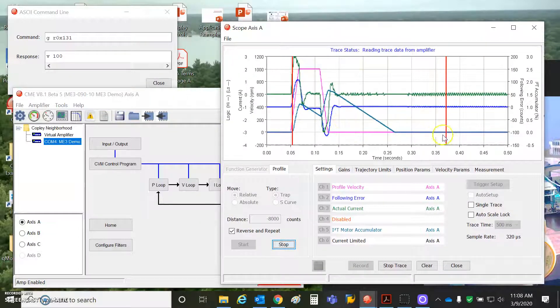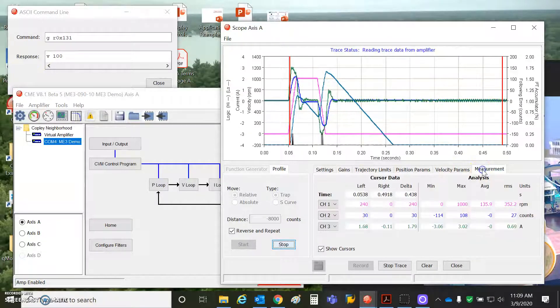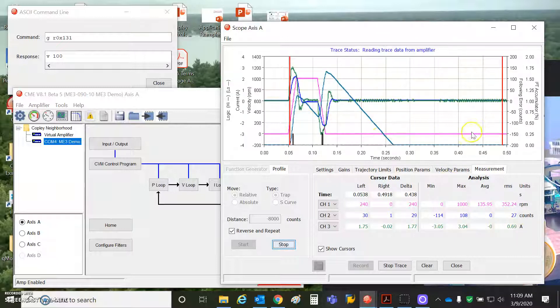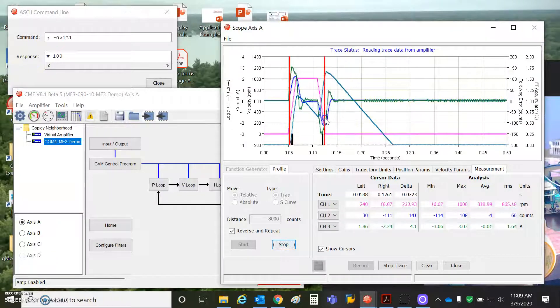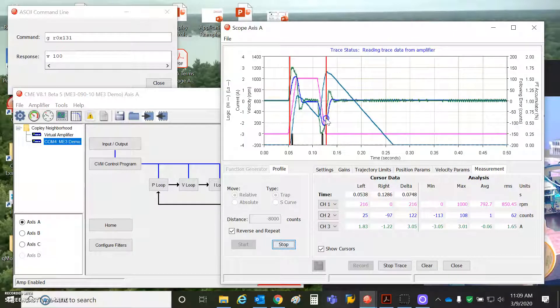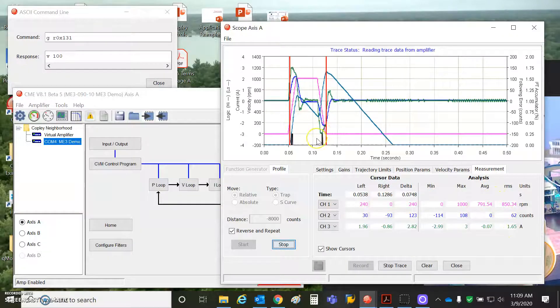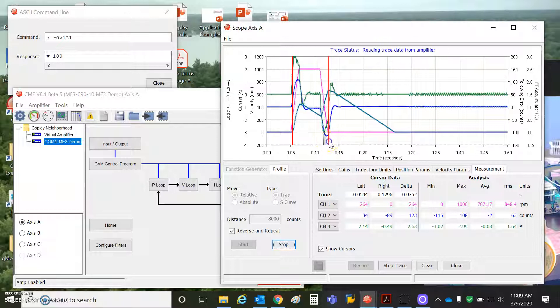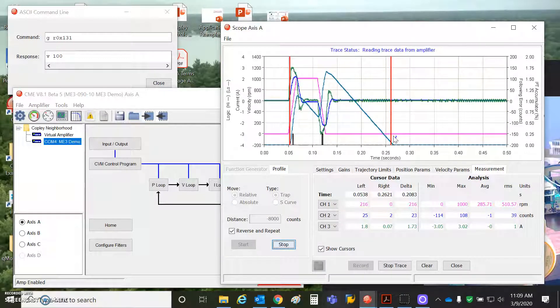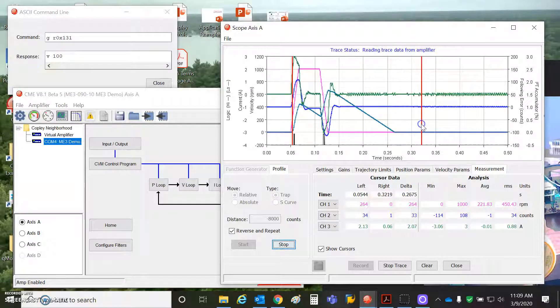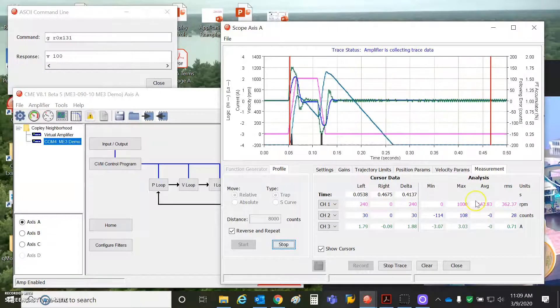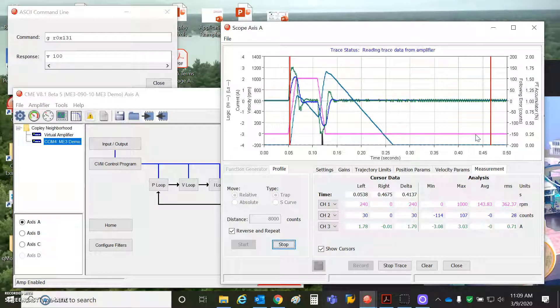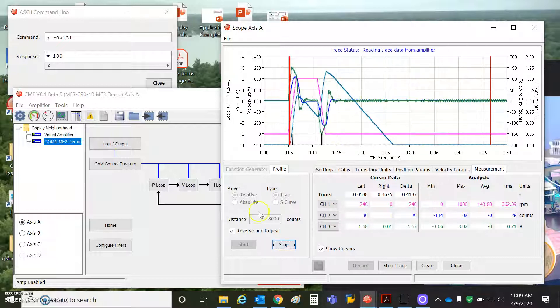Now, if we take a look at this over time, we have a duty cycle. And with the actual current value, we can see that the RMS current, while we're moving, I grab this and drag it over here. So while I'm moving, my currents are high. So on average, I got 1.65 amps RMS of the data during that move. And as long as I'm dwelling for a long enough period of time, you can see where the 1 amp point is here. The accumulator has gone back down. But if I had like a 50% duty cycle, my current would be on average RMS on the RMS of that. The average current is zero, but the RMS of that is less over that period of time.